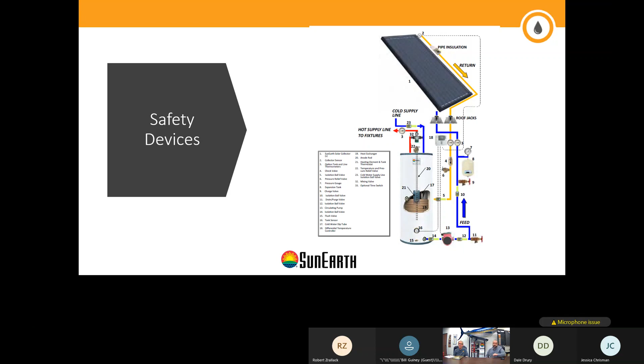Another thing that I personally consider a safety device is the gauges that show the pressure and the temperatures within the system. Because if you have a digital controller, yes, you're getting readings, but what if the sensor is not working properly? Having an analog gauge there that you can actually look at could be really useful. Depending on the design, that can again change. But I think those are also very important as far as safety and proper operation of the system.